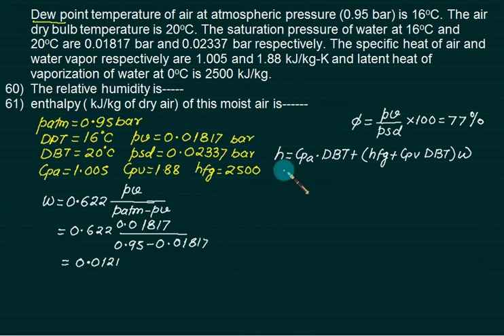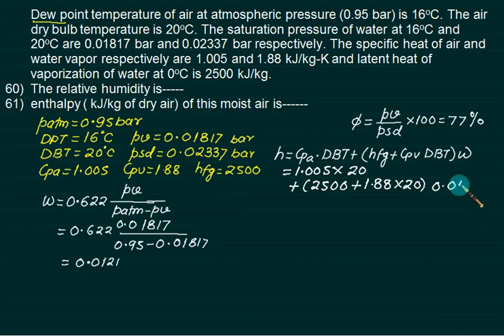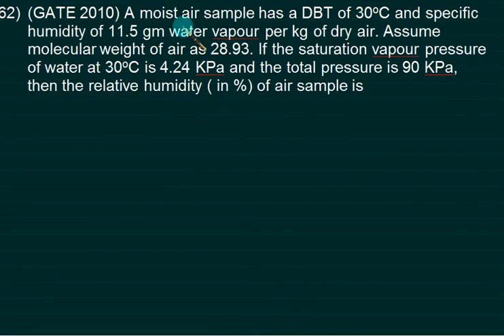Put this value: 1.005 times dry bulb 20 degrees Celsius plus HFG 2500 plus CP vapor 1.88 times dry bulb 20 multiplied by 0.0121. The answer is 50.8 kilojoules per kg of moist air sample.